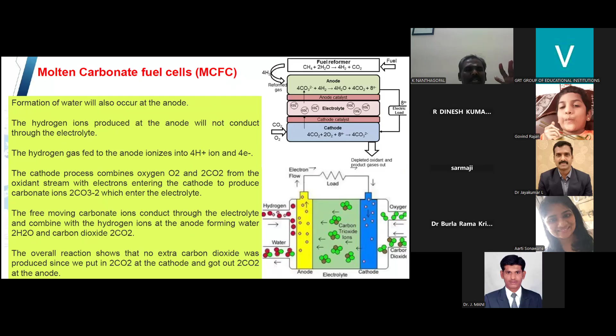The use of high temperature compounds of salt, carbonate salt like sodium or magnesium carbonate as an electrolyte gives efficiency ranging from 60 to 80%, with operating temperature around 650 degrees Celsius. Units up to 2 megawatts have been constructed so far, and designs exist for the molten carbonate fuel cell to generate power up to 100 megawatts. High temperature limits damage from carbon monoxide poisoning the fuel cell, which is another important limitation.